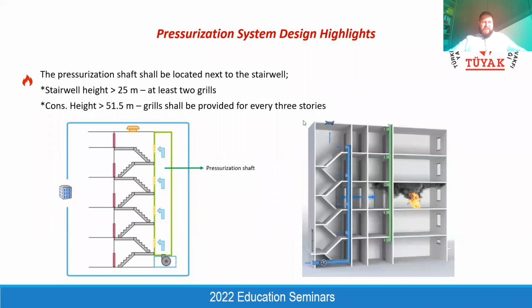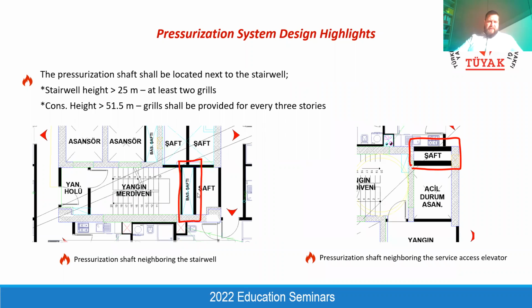It's very important. It changes all the design. No one can accept this kind of separation. That's why they will require you to redesign your building according to the fire code requirements. As you can see, we have a fire escape staircase here, and we have a pressurization shaft just neighboring the stairwell, and the grills are between the pressurization shaft and the staircase. And also the fire service escape stairwells are pressurized.